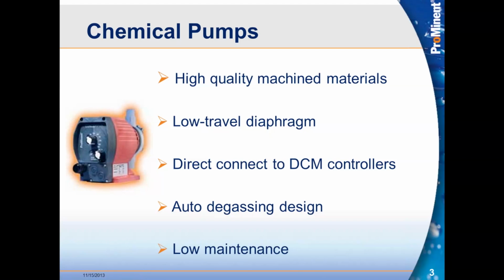The other benefit to our pumps, and this is a great tie-in with our DCM controller line we're going to be talking about in a few minutes, is that the pumps actually direct connect to our DCM controllers so that we can utilize the controller PID loop. Now, what does this mean for the pump? Well, the pump is a direct plug-in into the wall at a 120 volt hot outlet that's hot all the time. You run a low voltage cable from the pump over to the controller, and this eliminates any high voltage runs that need to be made. And then the DCM controller will not only tell the pump when to turn on, but it will also control the stroke of the pump for more precise dosing with the PID loop.